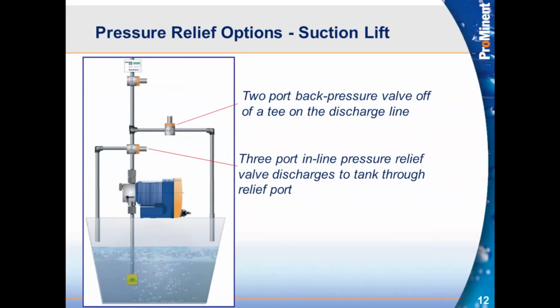Another example now in a suction lift application, it's kind of the same thing. We have the 3-port device that's going to relieve back into the tank. In this case, we're going to relieve back into the tank with the 2-port device as well. So either can be used in either application, and you see some arrangements here of how we would potentially do that. Chances are you're not going to see 2 pressure relief valves on one system. I don't remember seeing an application where we've done that in the past.